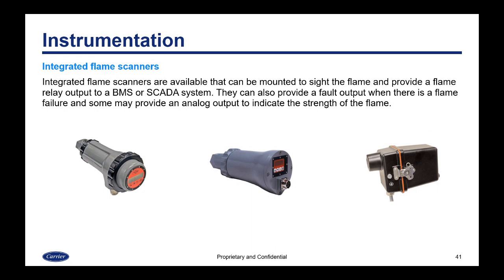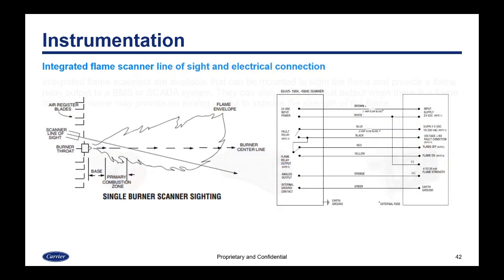Integrated flame scanners are available that can be mounted to sight the flame and provide a flame relay output to a BMS or SCADA system. They can also provide a fault output when there's a flame failure, and some may provide an analog output to indicate the strength of the flame. An integrated flame scanner is going to have outputs for the fault relay and the flame relay output, a power supply input, an analog output, and the schematic shows the scanner sighting from the scanner tube into the flame.